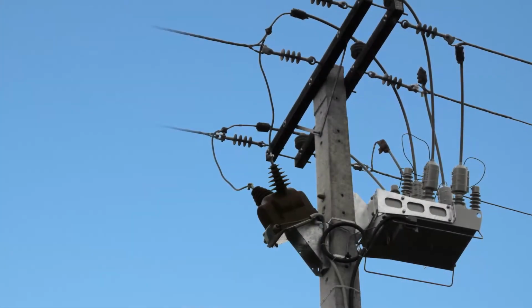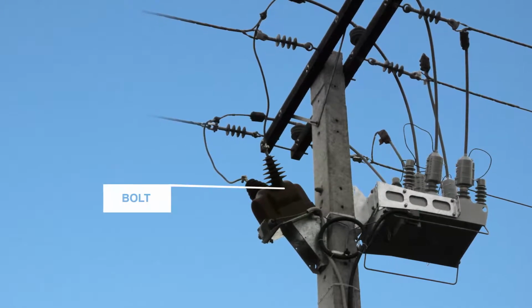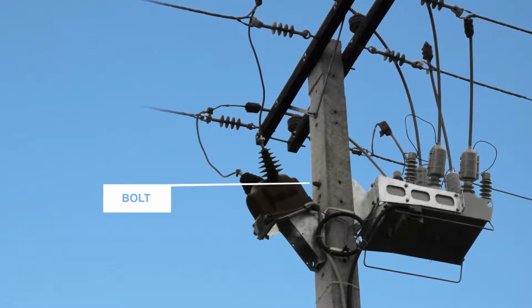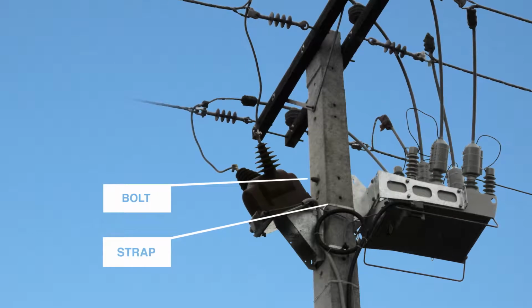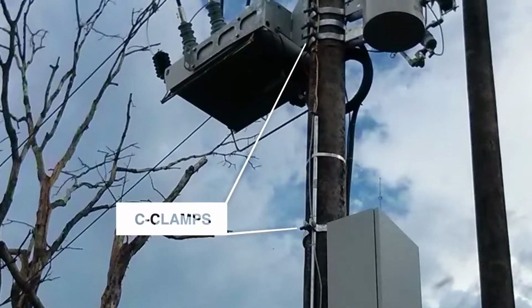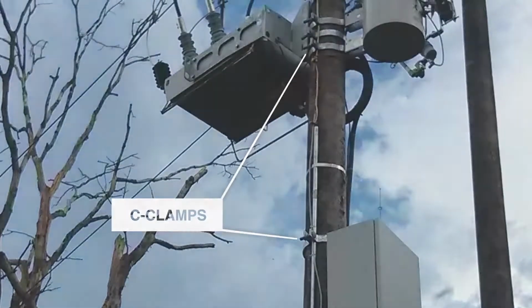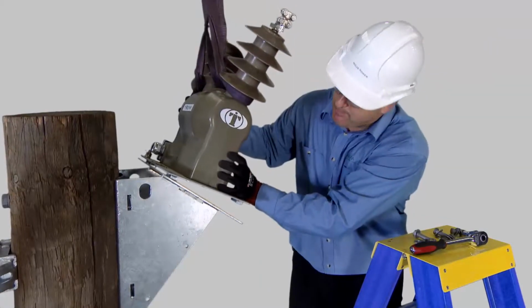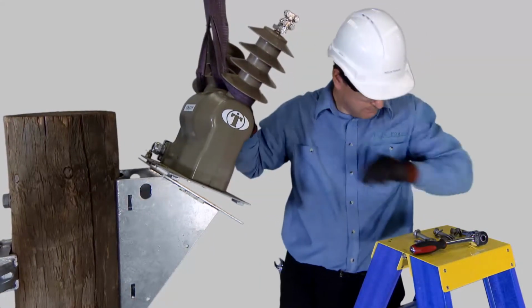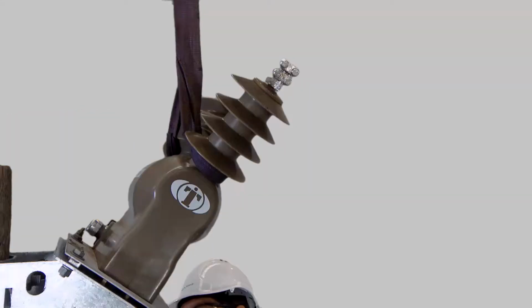For a concrete pole, the recloser can be fixed with a single bolt through the top hole in the bracket and a metal strap on the lower part of the bracket. C-clamps can also be used. Lift the VT onto the bracket using a soft sling and secure with nuts and bolts.